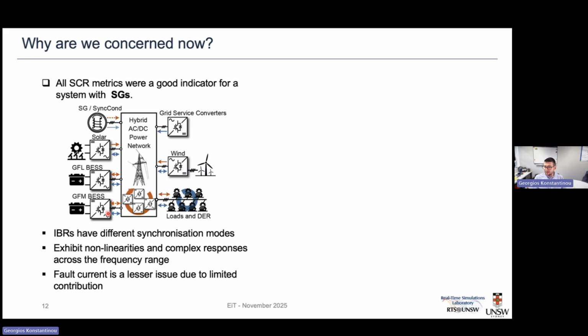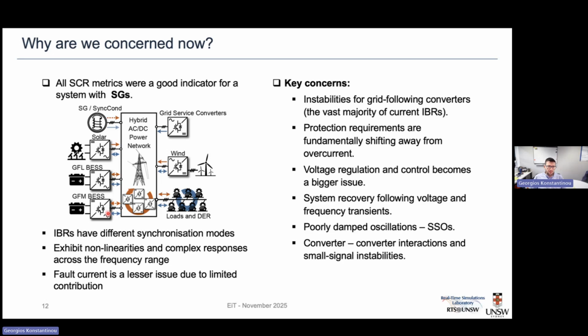Also, our power electronics are current limited. We cannot get the very high currents we'd get from a synchronous generator during a fault. Because they're current limited, the fault contribution, the amount of current coming out of them during a fault, is much lower. So if we look at the previous definitions, we'd end up with very low fault current levels, which tells us that simply using fault current doesn't necessarily tell us the whole story about the strength of a system at a particular location.